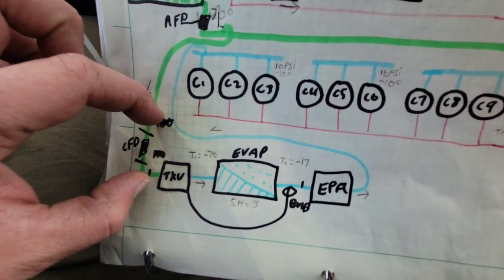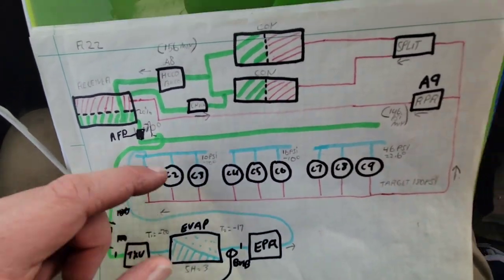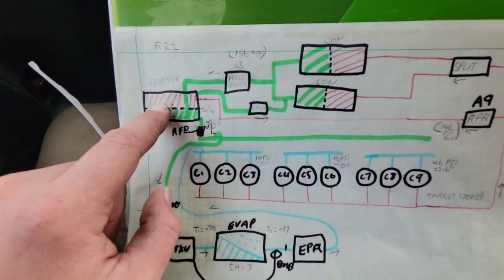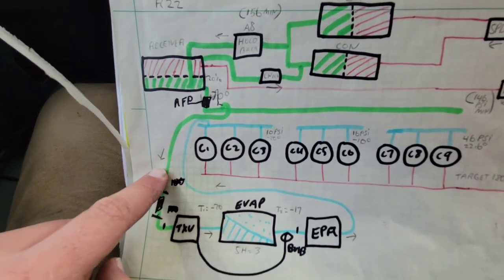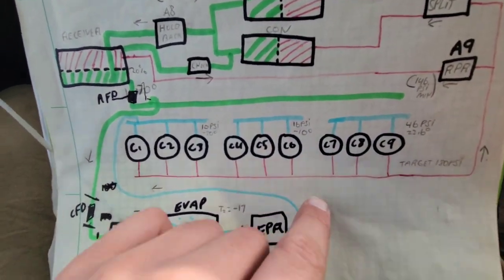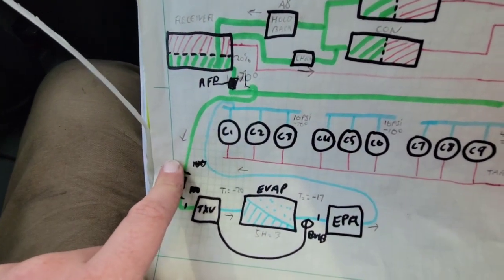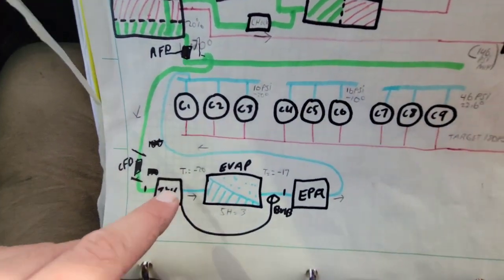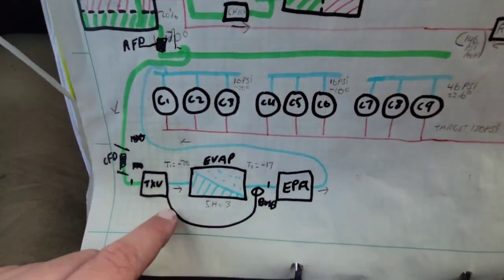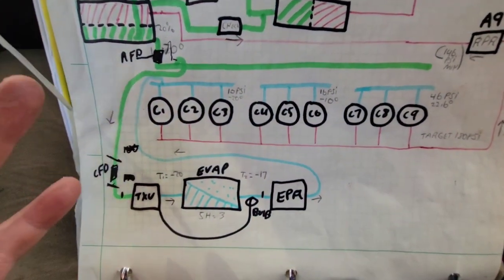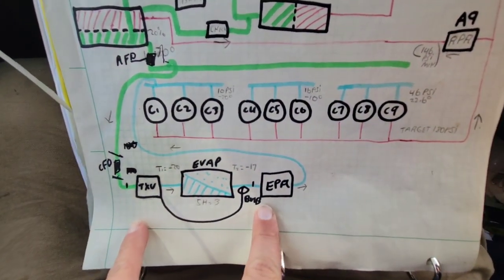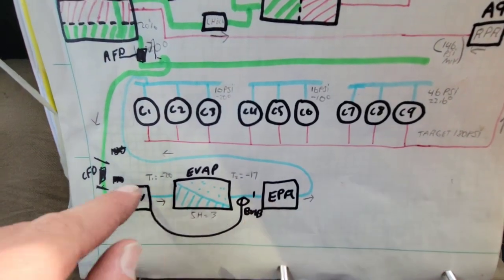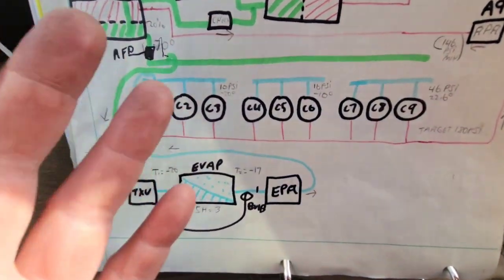Okay, if that's all good, the only thing left, right? Pressures are right. Refrigerant level is right. Flow is right. Okay, EPR is feeding, or suction solenoid is feeding. Okay, everything is feeding to the what? The TXV. This is the only thing remaining at that point. And how do you test it? Superheat. Okay, you test your superheat. Is your superheat right? No.